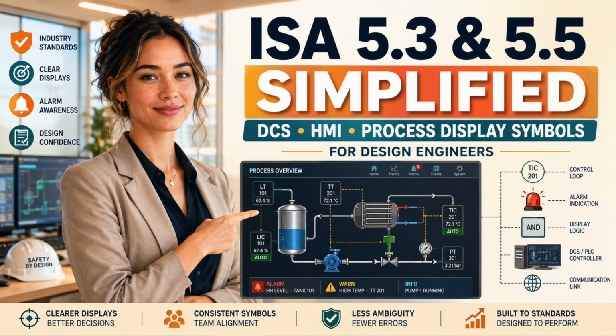Define a project-wide color philosophy before graphic production begins. Decide how the interface will represent emergencies, warnings, normal operation, unavailable equipment, maintenance, inhibited alarms, bypassed protection, bad quality, stale data, forced values, simulation, and communication failure. Never allow each package supplier to bring its own color vocabulary into the control room. The operator should not need to remember which vendor designed each screen before interpreting its meaning.